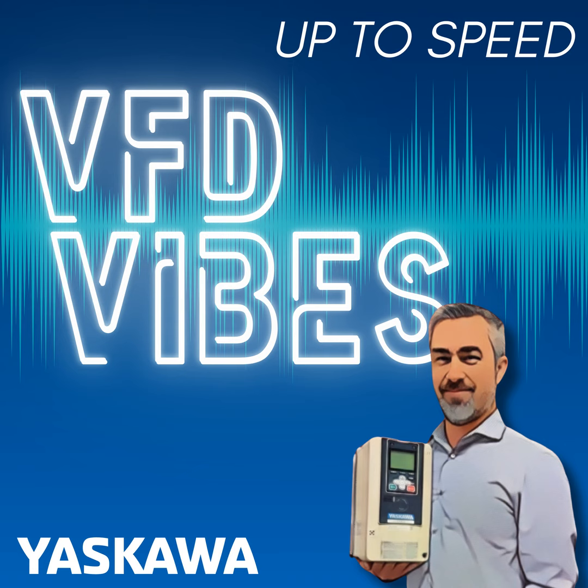Now that your VFD knows your motor, let's talk about how it behaves under changing conditions. Many systems don't run at full load all the time, so how do we keep efficiency up when the demand drops? This is where unique product features like energy savings mode come in. It's essentially the opposite of torque boost. Instead of adding voltage to create more torque in times of need, energy savings mode reduces voltage during light loads to minimize power draw. Great for fans and pumps that don't always need full speed, and again, great for the longevity of your equipment.